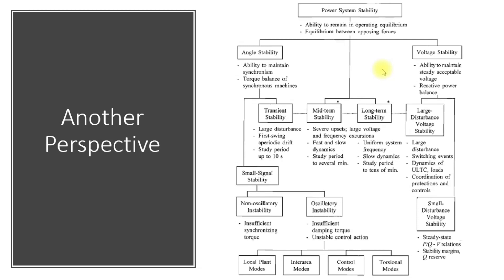Another reason for oscillatory instability is unstable control operation. When exciter models, generator models, and governor models are not tuned properly, instead of damping oscillations, they provide positive feedback that increases oscillations. The three main types of oscillatory instability are inter-area oscillations, intra-plant (within-plant) oscillations, and torsional oscillations. Torsional oscillations refer to stresses on the shaft of the system.